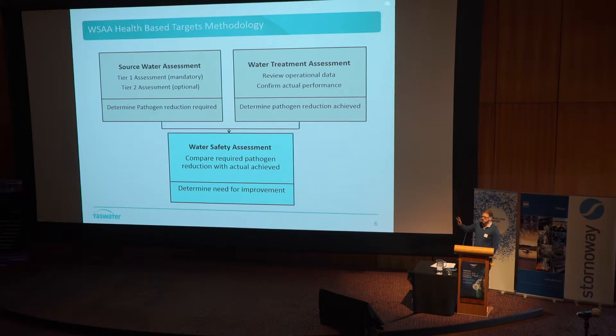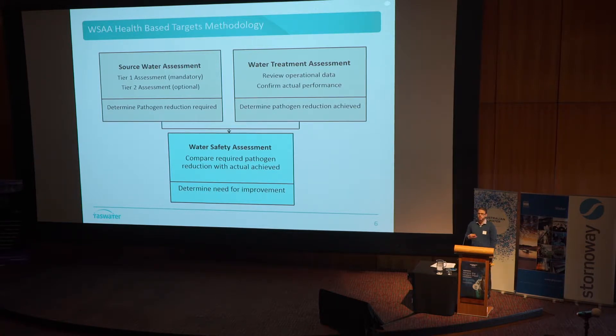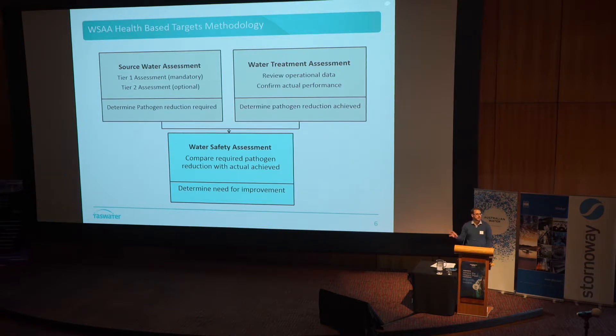This is essentially a graphic of how the WSAA health-based target methodology works. We start on the left, which is the source water assessment — that's really where you're quantifying your pathogen risk. There are two approaches: tier one and tier two. In tier one, you're using E. coli as a surrogate for pathogen concentrations, while in tier two you're actually doing direct pathogen monitoring. Once you've determined your pathogen risk, you then go to the second phase and assess what your treatment process can do to make the water safe. You put both together and say: where am I now — am I safe or am I not?